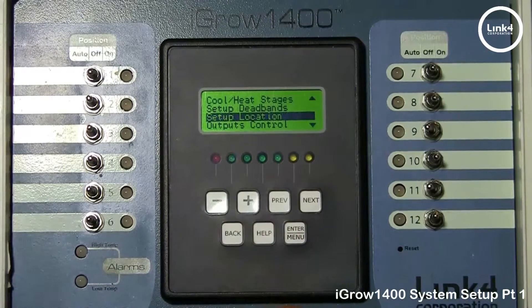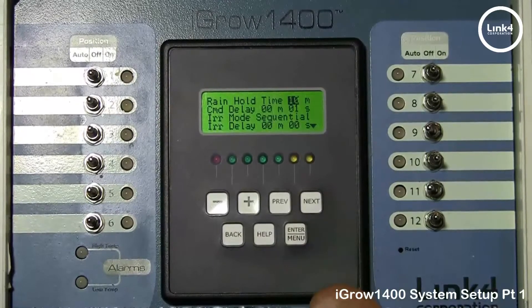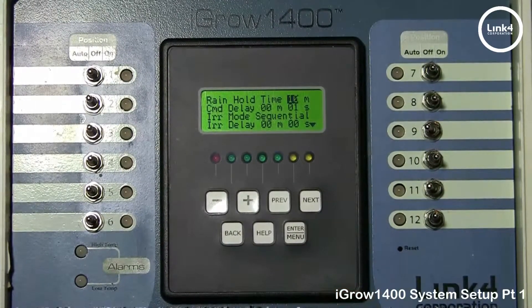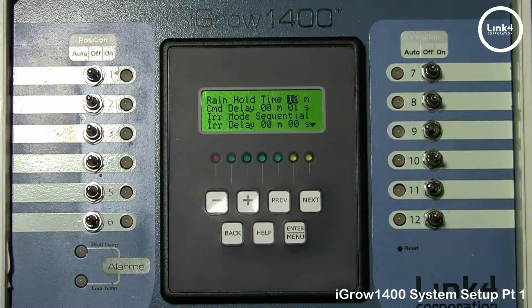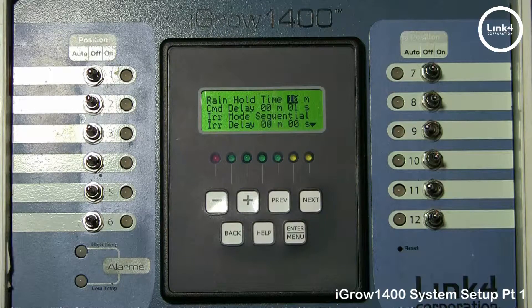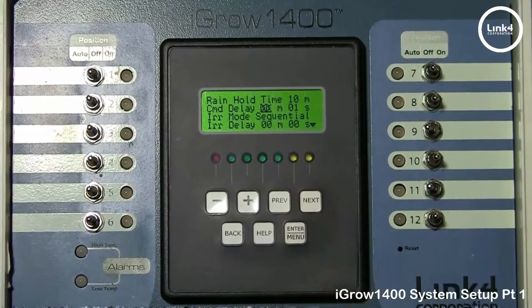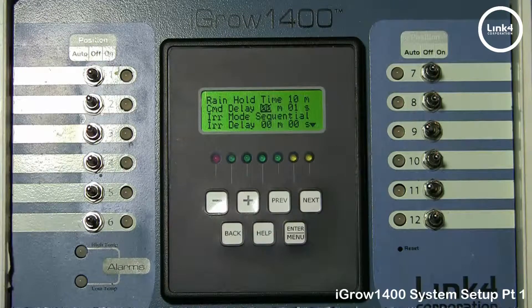Hit back and go to Outputs Control. Outputs Control has several different features: Rain Hold Time, Command Delay, Irrigation Mode, and Irrigation Delay. Rain Hold Time is the parameter that lets you choose how long you want the rain override condition to persist after the rain status goes from yes to no. This keeps intermittent rain from causing the vents to keep opening and closing. Command Delay is the time between commands to change the equipment's states — the shortest time permitted for switching equipment.